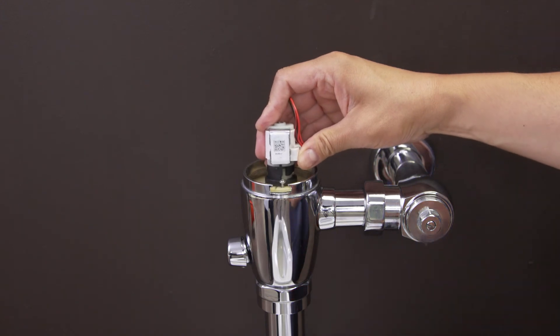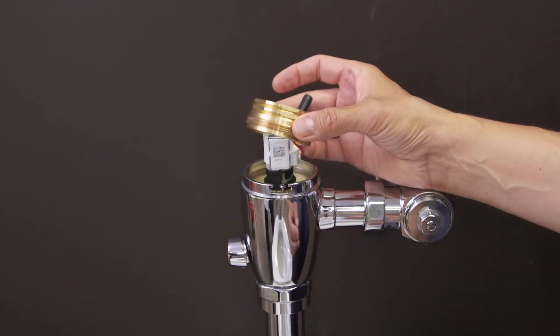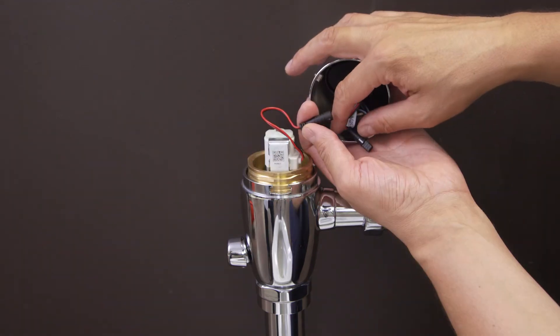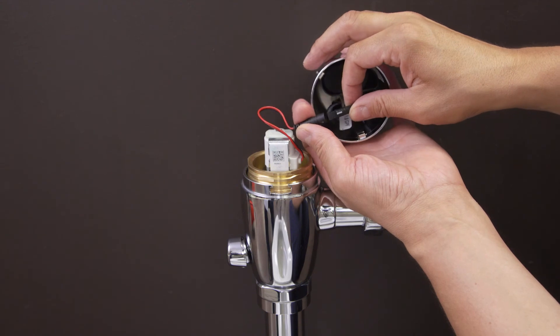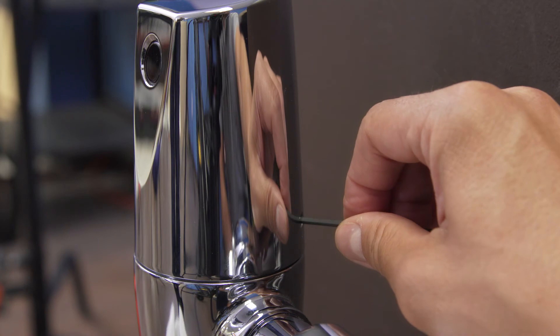Push the sub assembly down into the flushometer. Feed the wire through the bonnet nut and tighten the nut to secure the assembly. Now attach the sensor wire. Replace the cover and tighten the set screw.